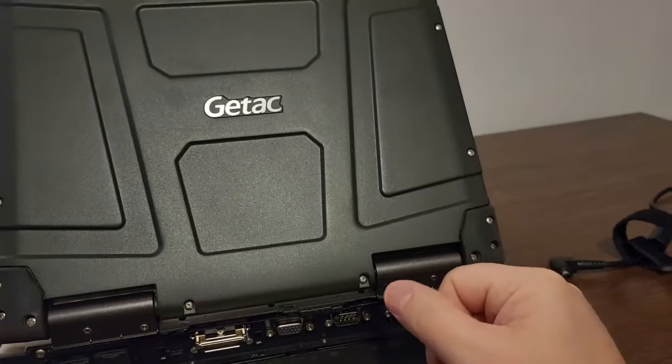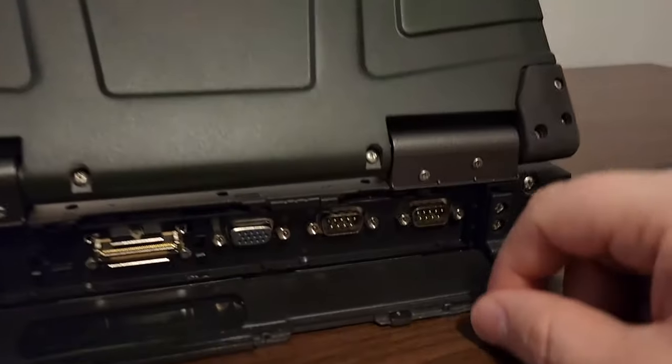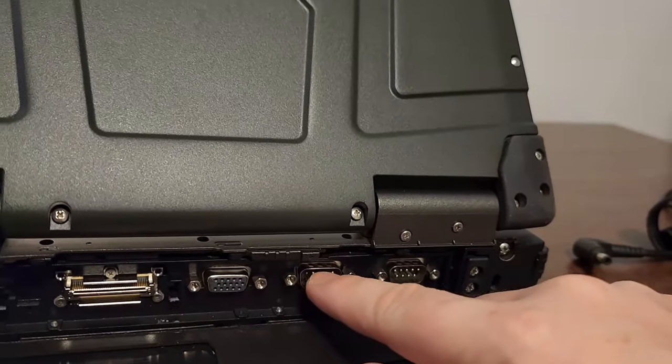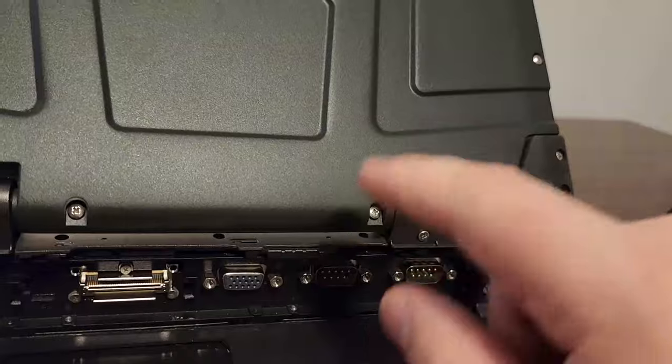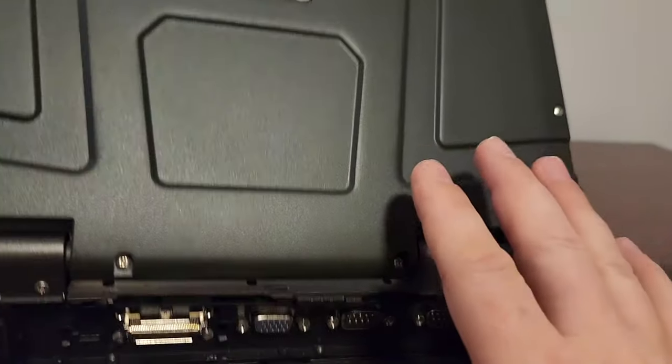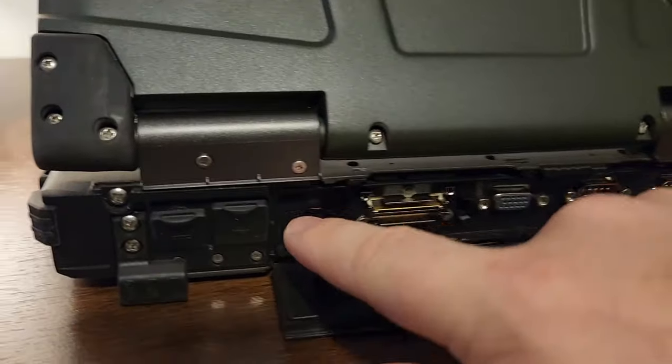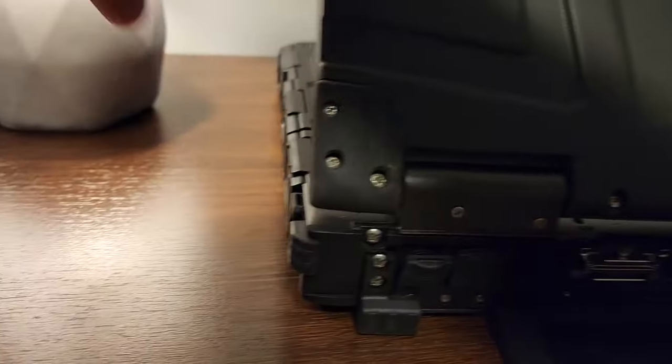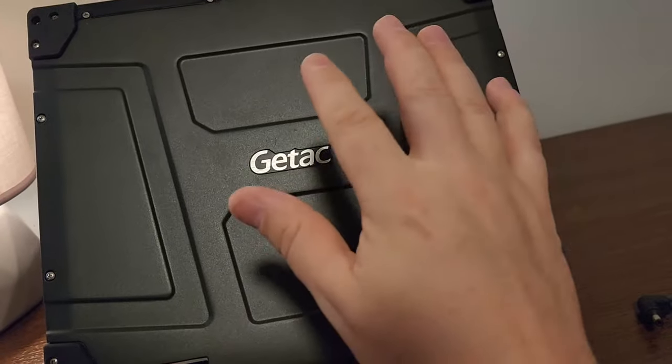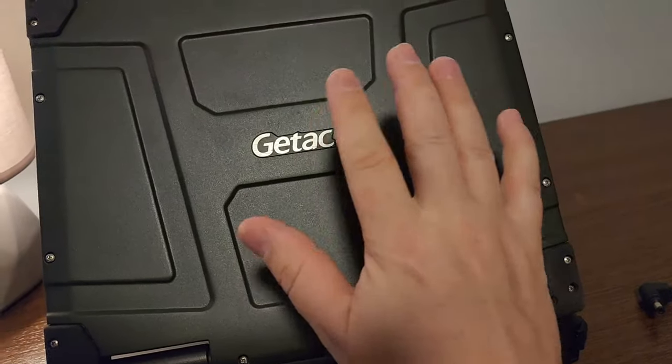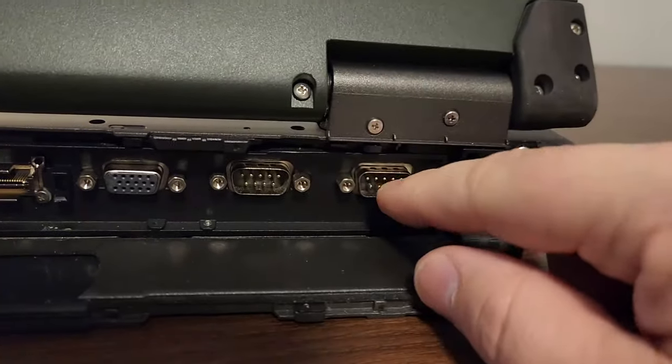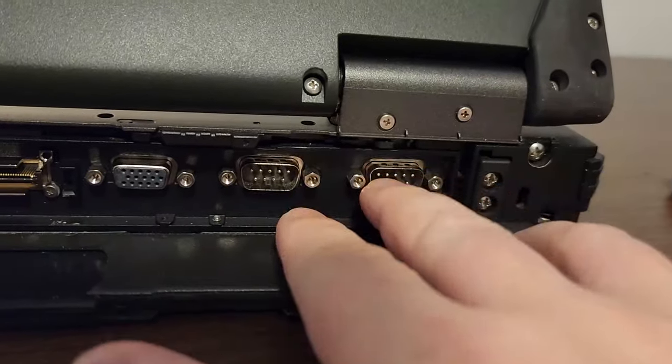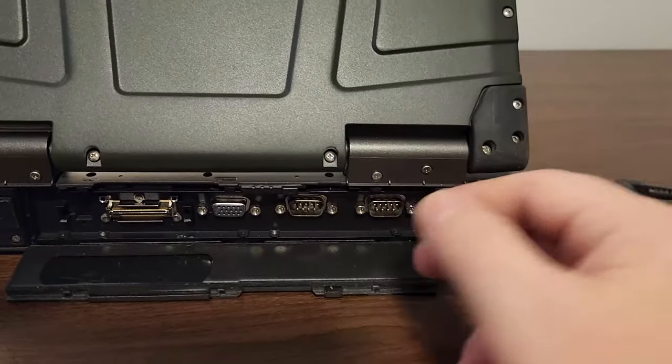One problem is when you plug into a new USB port, the COM port always changes. Let's say I'm calibrating Alaris pumps - I can set it up on this COM port and as long as I plug into this port, it will always stay the same COM port. If I move my dongle to different USB ports, I have to go back inside the software and change the COM port - that's so frustrating. I really dig that I have native serial ports, and two of them. Technically I could get two softwares running at the same time and double my output.